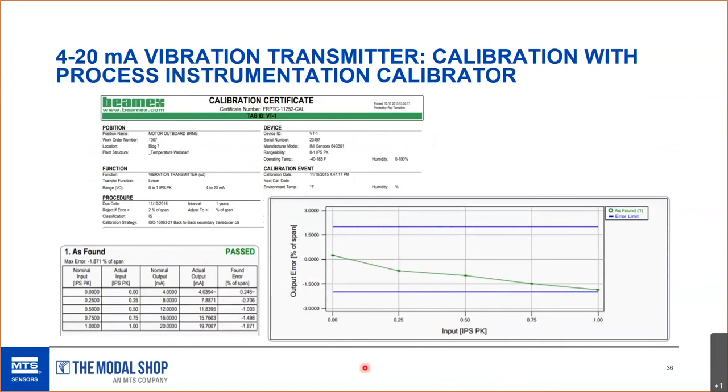You can also calibrate and test 4-to-20 mA vibration transmitters with a process instrumentation calibrator. It supplies power to the sensor just like any other 4-20 mA device — your portable shaker serves as the equivalent of a pressure hand pump. You can perform a linearity test and calculate percent-of-span output error. We use a Beamex process instrumentation calibrator, but many products on the market work for this, and they generate reports useful if you're audited for vibration instrumentation calibration.